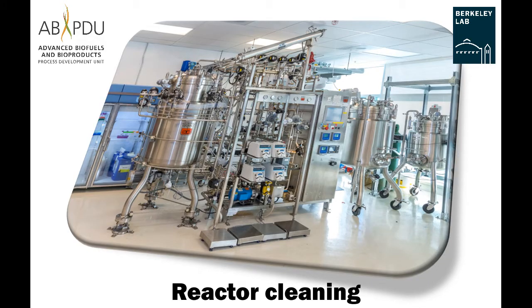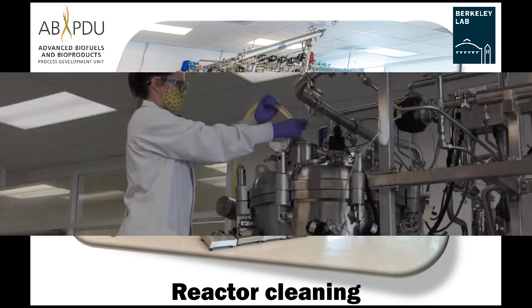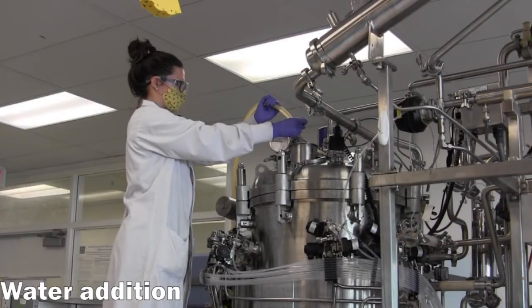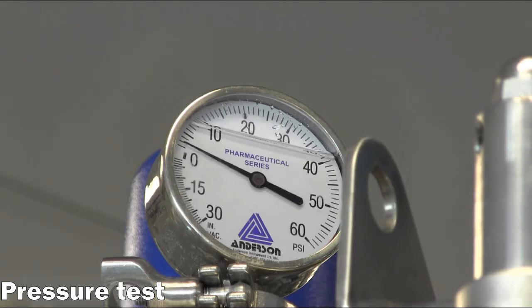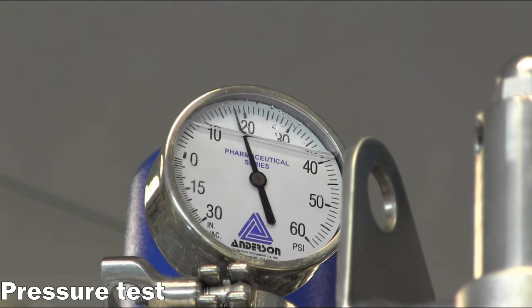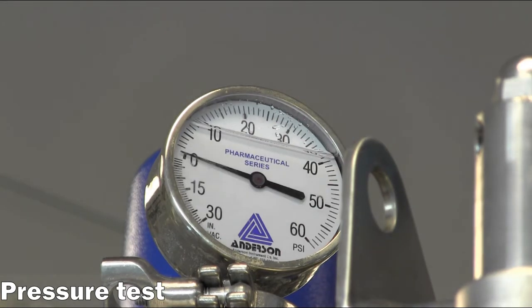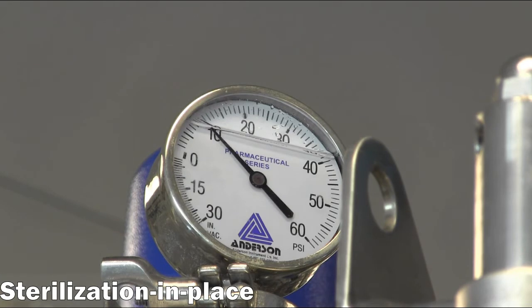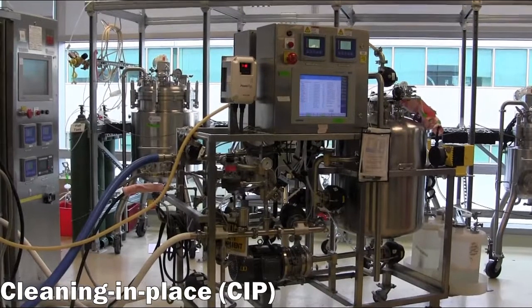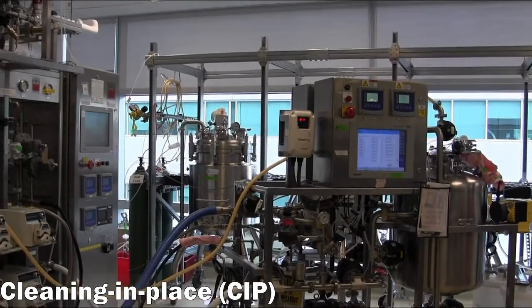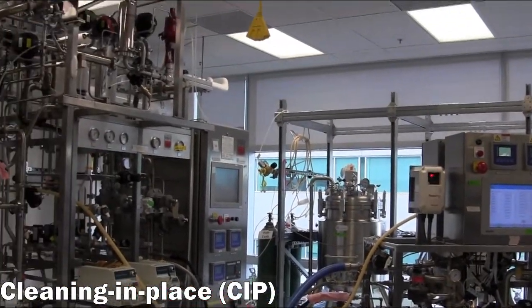Reactor cleaning. To clean the reactor, add water and carry out a pressure test, followed by an SIP cycle to heat kill any biological material that remains in the reactor. After draining the reactor, we can begin setting up the vessel for cleaning in place, or CIP.